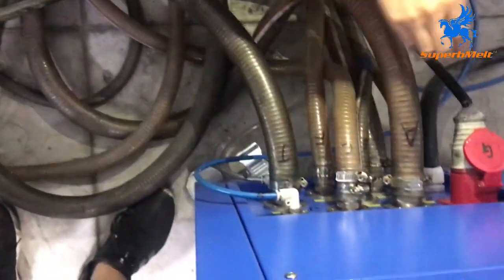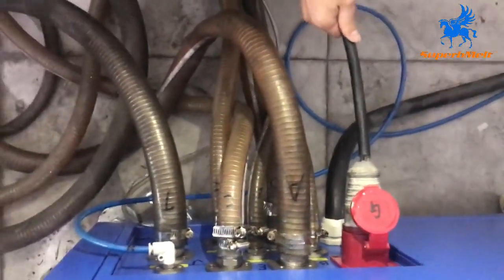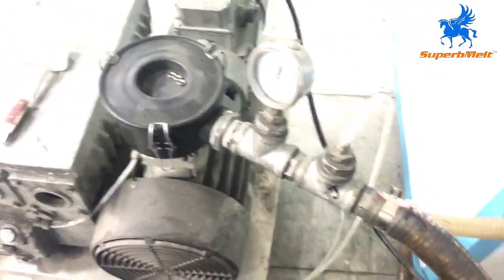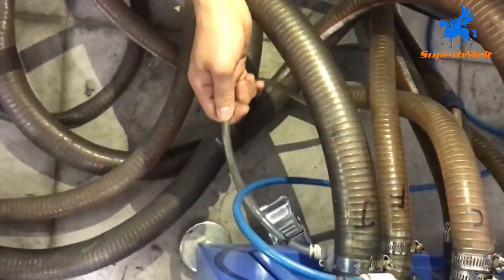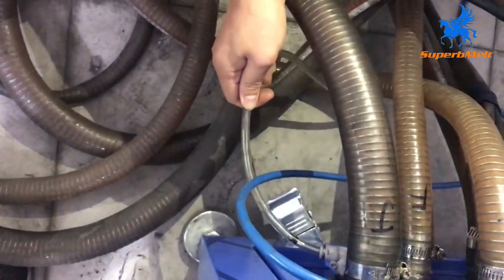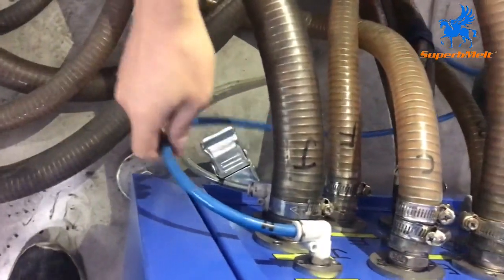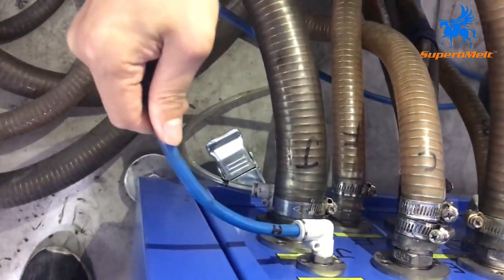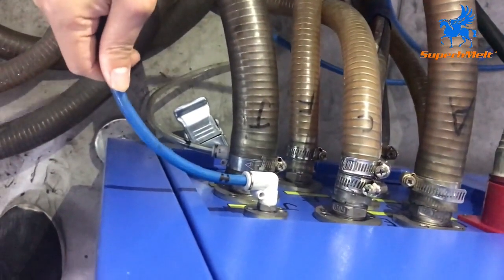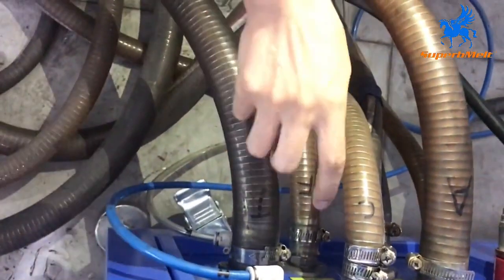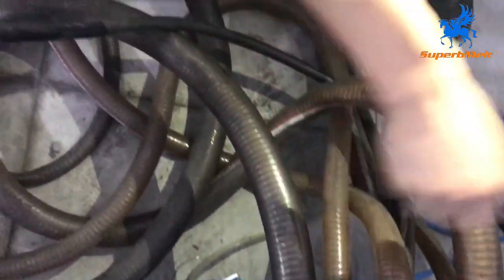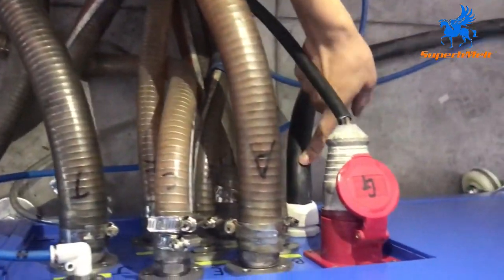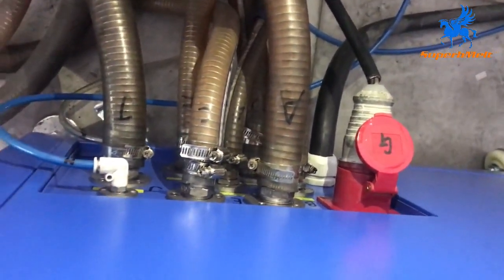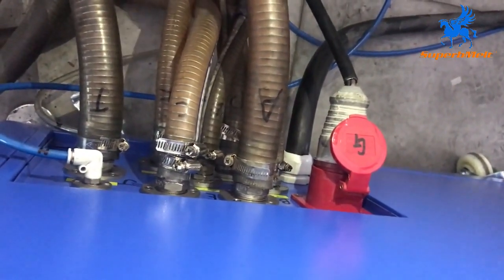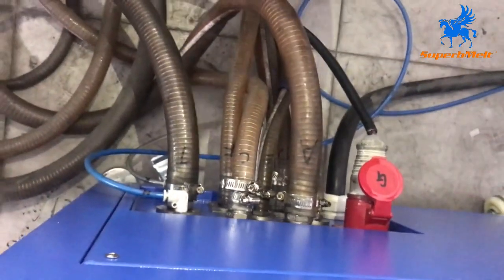Six lines. For this one is the vacuum pump power. And this line is the air compressor. This one connects to the protect gas like argon. Normally we use argon. This pipe J is the vacuum pump pipe connection. This line is the power line. The power must attention that is 3-phase 380. That's all connection. We already mark all numbers in the machine.